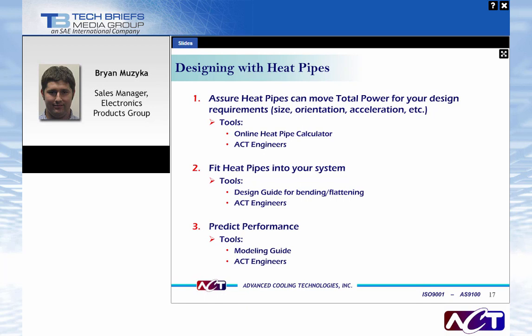There are three main steps to designing heat pipes within your system. The first is to assure that heat pipes can move the total power for your design requirements — inputting size, orientation, and other parameters to output the capillary curve. ACT has created an online heat pipe calculator where engineers can calculate capillary limits and pick the appropriate number and size of heat pipes. The second step is fitting heat pipes into your system, with a design guide covering bending, flattening, and integration techniques. The third is performance predictions — modeling guidelines are available online to help engineers model heat pipes for their system parameters.